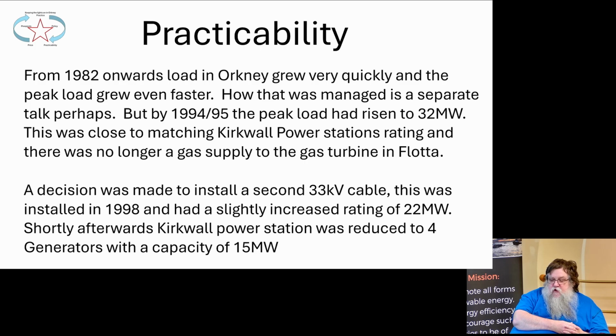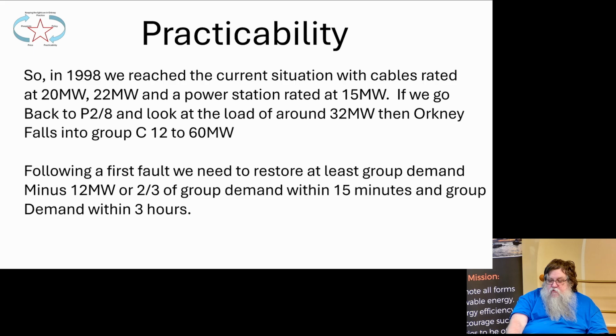This was installed in 1998 and had a slightly increased rating of 22 megawatts. Shortly afterwards, Kirkwall Power Station was reduced to 4 generators with a capacity of 15 megawatts. So in 1998, we reached the current situation. There's not really been any significant change since 1998, with cables rated at 20 megawatts, 22 megawatts, and a power station rated at 15 megawatts.